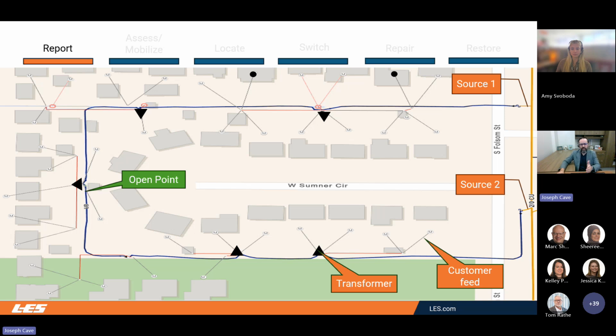Let me set the stage here. This is a map of what our system looks like as our operators see it. On the top right you see source number 1 feeding this neighborhood, coming off an overhead line, with the blue line showing an underground feed through the neighborhood. Below that there's source number 2, so there are two sources to this neighborhood. On the left you'll see an open point — our system is segmented throughout different areas with open points. We've got two sources into this neighborhood, but not both are connected to all the lines. You'll also see black triangles, which are transformers; each one steps the voltage down to the appropriate level for that equipment. And in the bottom right corner is our customer feed — the low voltage wires that go to the meter at the house or business.